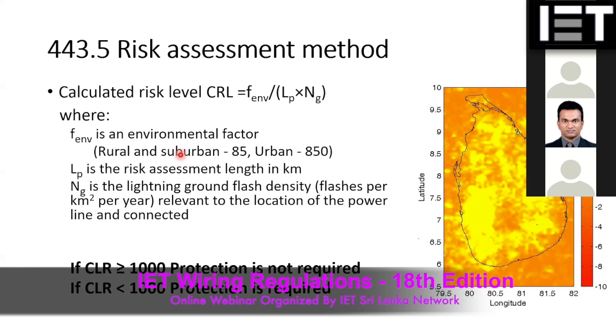What it says is, if this CLR is more than 1000, then you don't need such protective devices, and if the risk level CLR is less than 1000, then you have to have surge protective devices. And if you are not calculating risk, then it's compulsory to use surge protective devices. That's what the regulation says. So now that is a new requirement. These are new additions to the regulation.